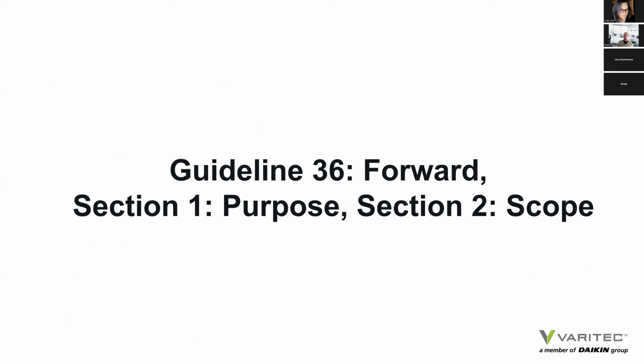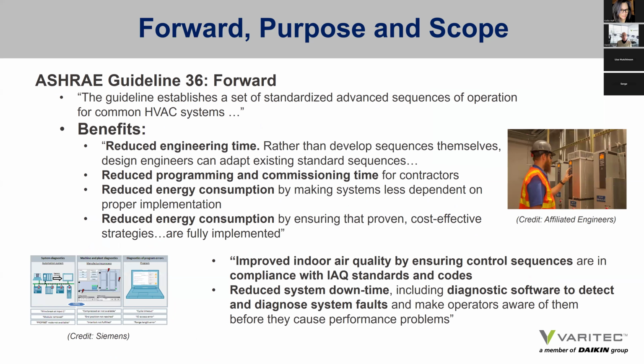So let's look at the guideline itself. Let's begin by making sure we understand more fully what its purpose is. In the foreword, the guideline says it establishes a set of standardized advanced sequences of operation for common HVAC systems to reduce engineering time, reduce programming and commissioning time, and reduce energy consumption by making systems less dependent on proper implementation, and by ensuring that proven cost-effective strategies are fully implemented. They can also improve indoor air quality by ensuring control sequences are in compliance with IAQ standards, specifically 62.1, and municipal local codes.